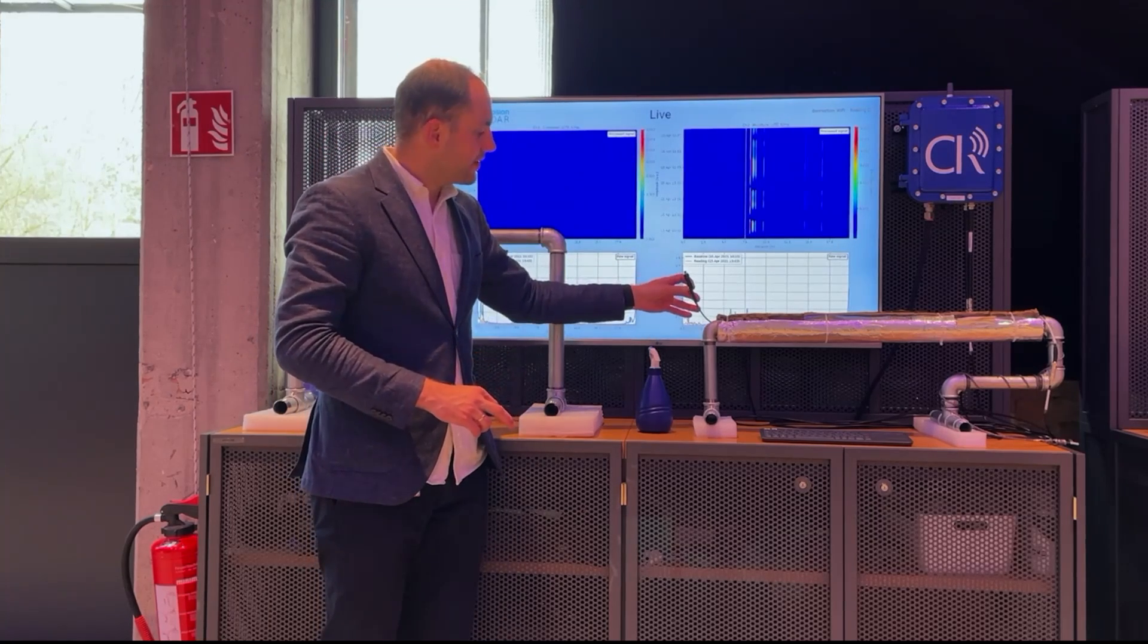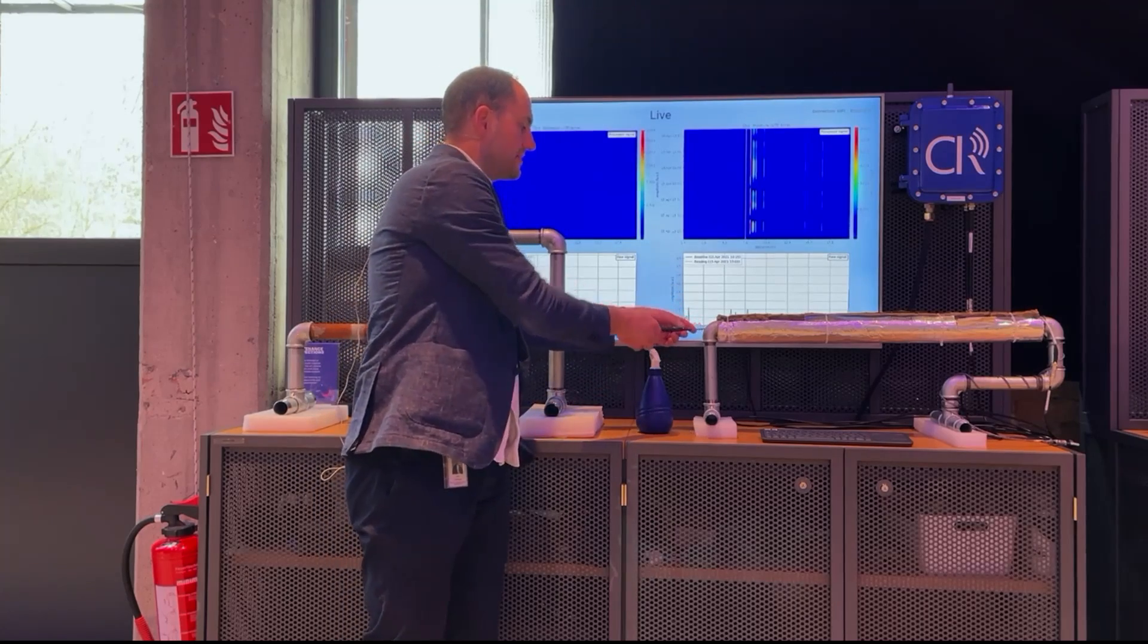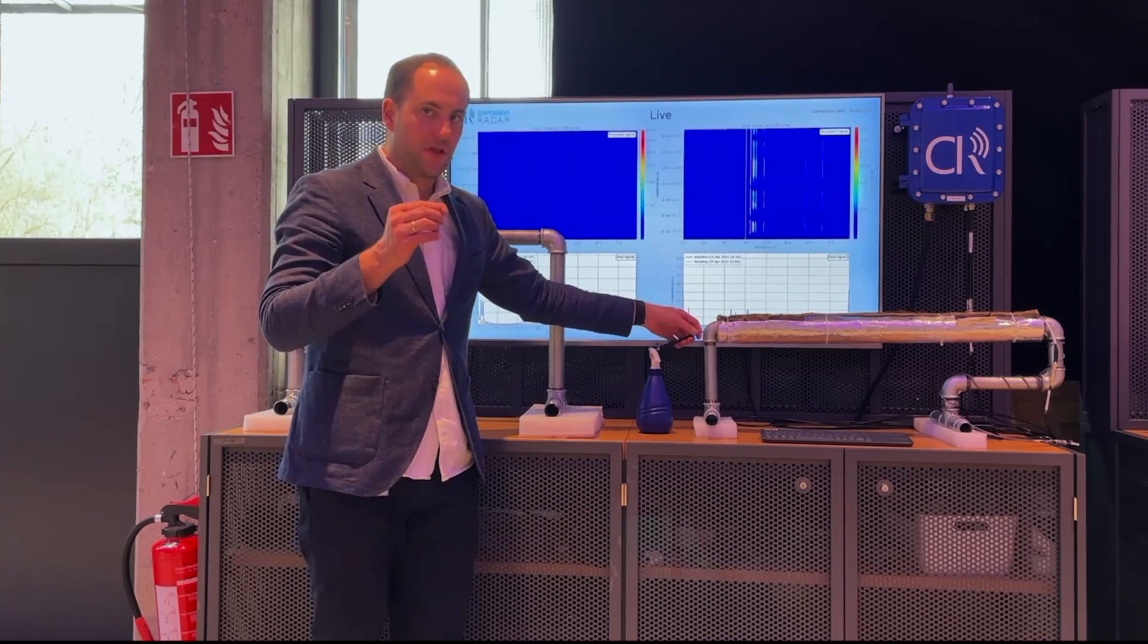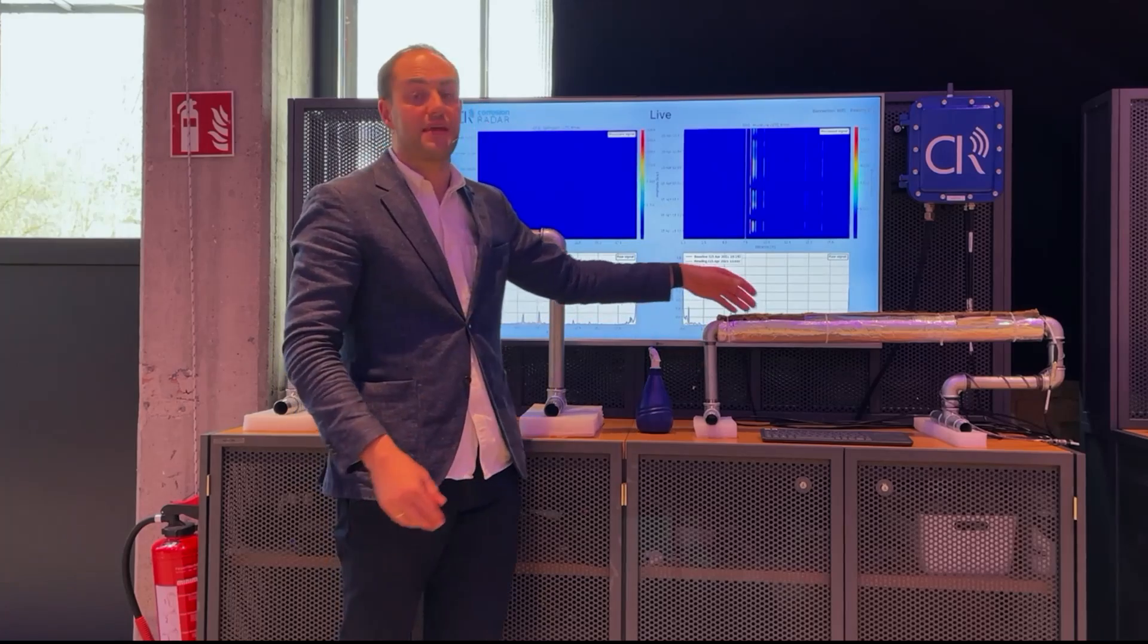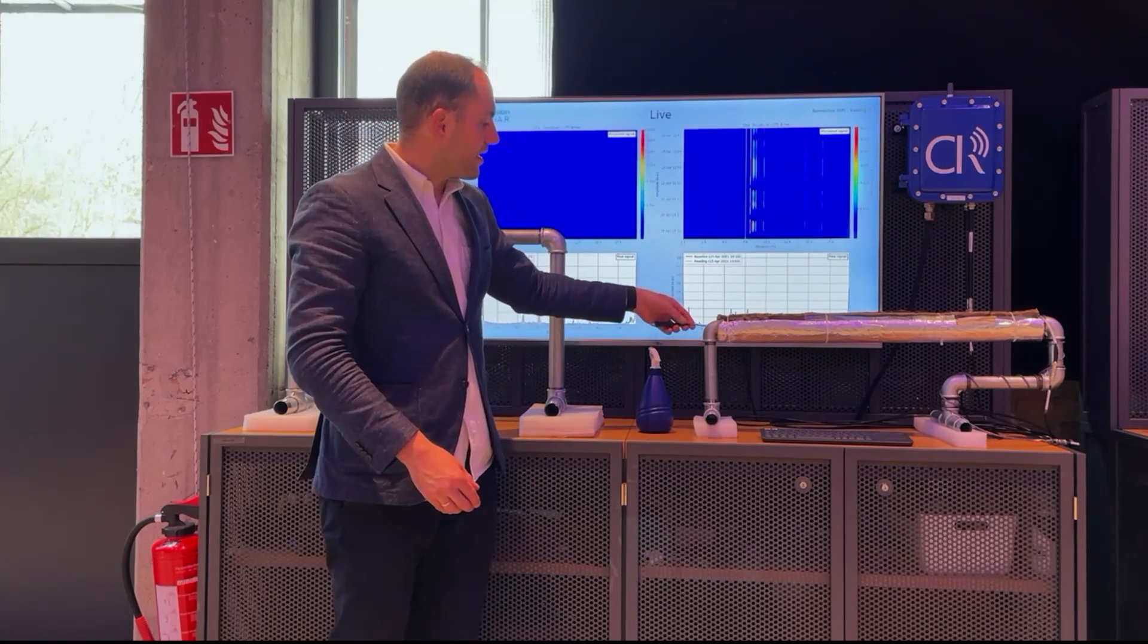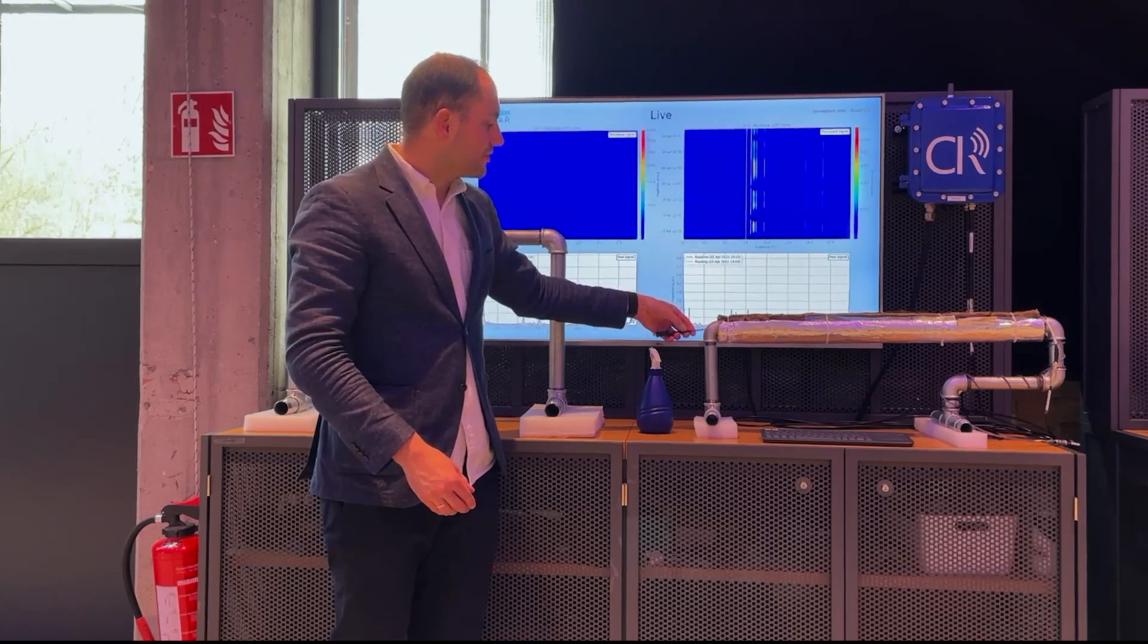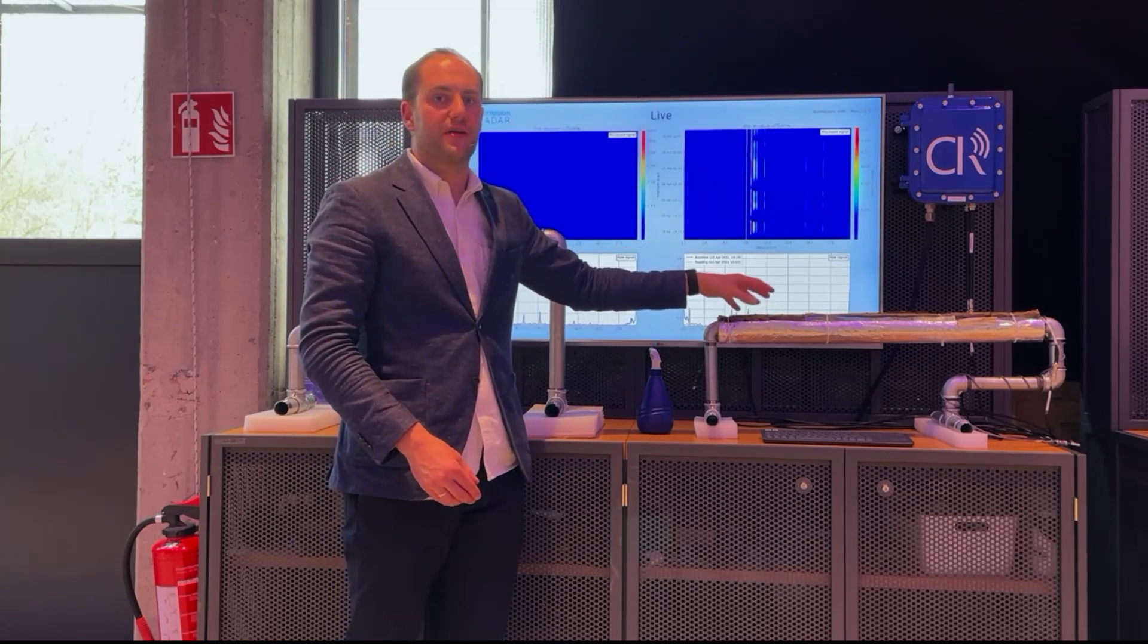The detector itself is basically replicating the corrosion which happens to the asset itself. When you have a closer look at it, you can see that this detector is basically wrapped around with a cable which starts corroding in the same speed like the asset. This way, you can easily detect if there is corrosion already on this particular part on your asset.